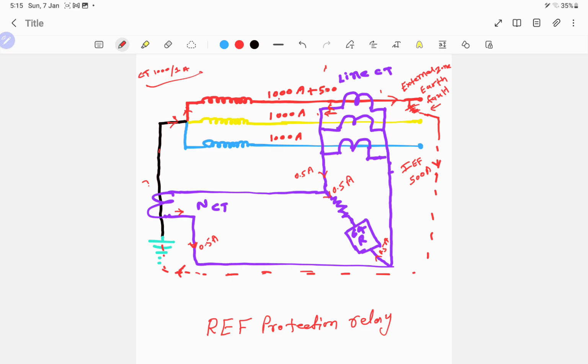Now what happened is, because there is 500 amps extra flowing through the R phase, the winding is now unbalanced. So the net secondary current from the CT will be 0.5 ampere, because this 500 ampere adds an extra 0.5 ampere in the circuit. So the net current, 0.5 ampere here, will flow through the line CT, because the primary current is flowing here. So the CT will sense 1500 amps, and these CTs will sense only 1000 amps. So 1 amp, 1 amp, and 1.5 amp. So the resultant current of 0.5 amp will flow from the secondaries of the line CTs, which are all connected in parallel.